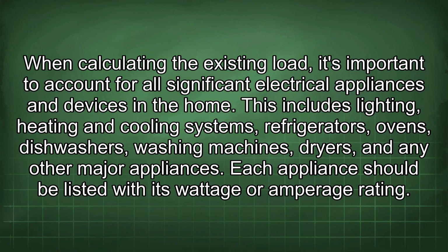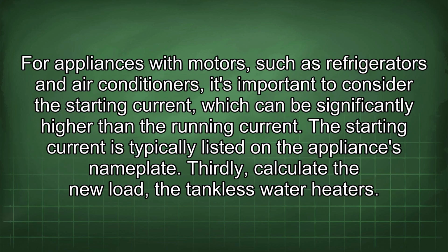When calculating the existing load, it's important to account for all significant electrical appliances and devices in the home. This includes lighting, heating and cooling systems, refrigerators, ovens, dishwashers, washing machines, dryers, and any other major appliances. Each appliance should be listed with its wattage or amperage rating. For appliances with motors, such as refrigerators and air conditioners, it's important to consider the starting current, which can be significantly higher than the running current. The starting current is typically listed on the appliance's nameplate.